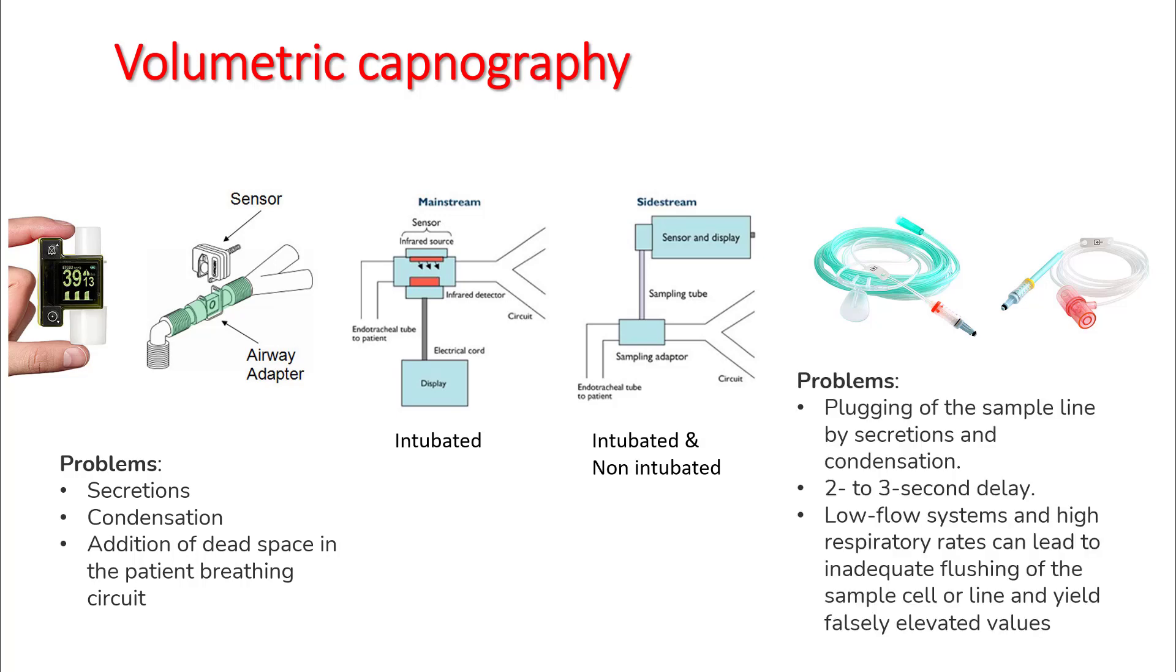The common problem with either of these methods is secretions and condensation. In addition, the mainstream capnography method can add dead space to the patient's breathing circuit, as shown in the green area.